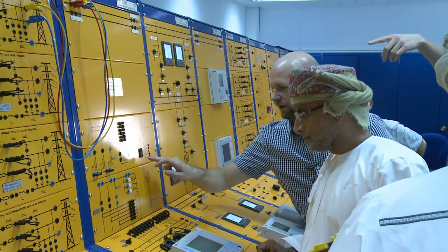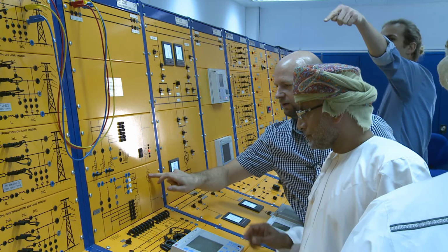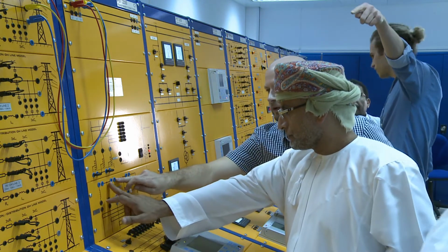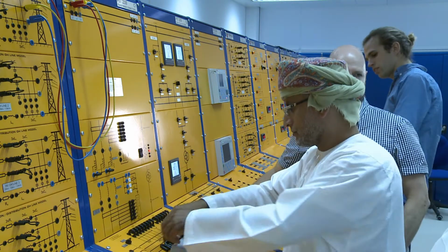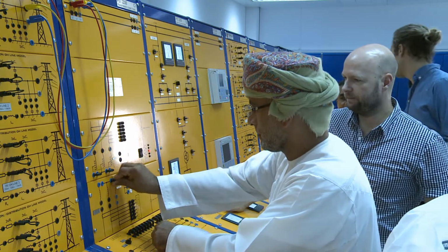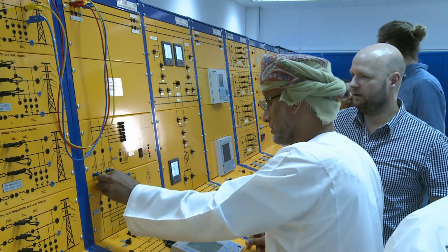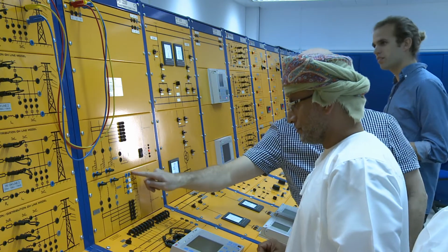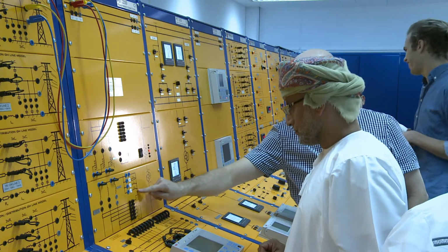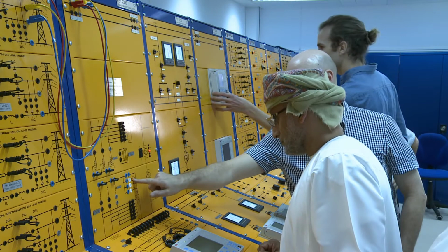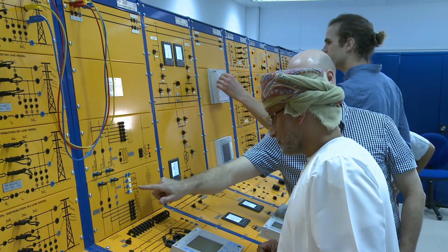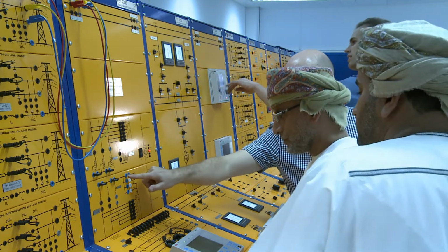So this one is the secondary side. We need to make a neutral point here and connect them to the line. This neutral point we can put to earth, either by an impedance, by a resistor, by Petersen coils, or directly.